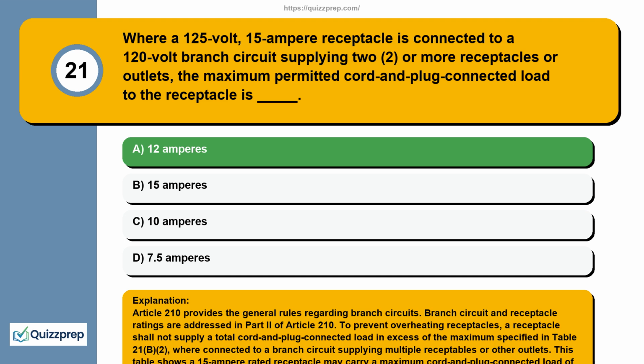Article 210 provides the general rules regarding branch circuits. Branch circuit and receptacle ratings are addressed in Part 2 of Article 210. To prevent overheating receptacles, a receptacle shall not supply a total cord plug connected load in excess of the maximum specified in Table 210.21(B)(2), where connected to a branch circuit supplying multiple receptacles or other outlets. This table shows a 15 ampere rated receptacle may carry a maximum cord plug connected load of 12 amperes under this condition.